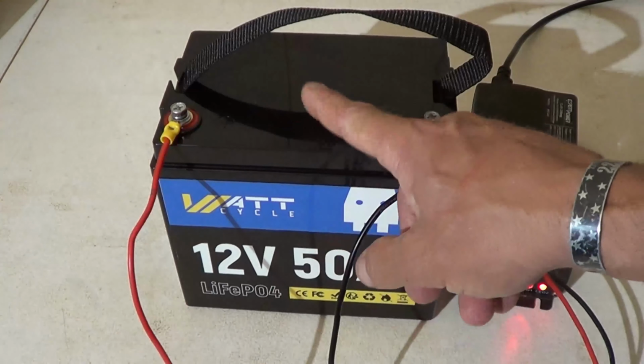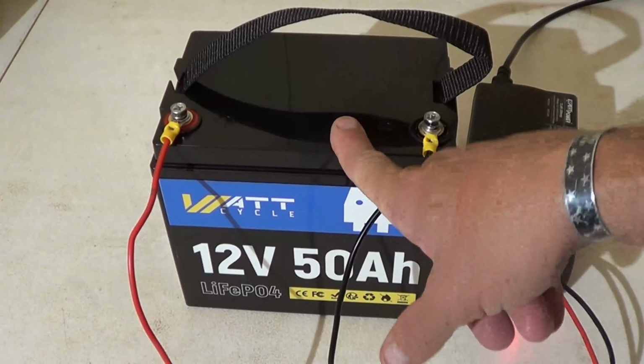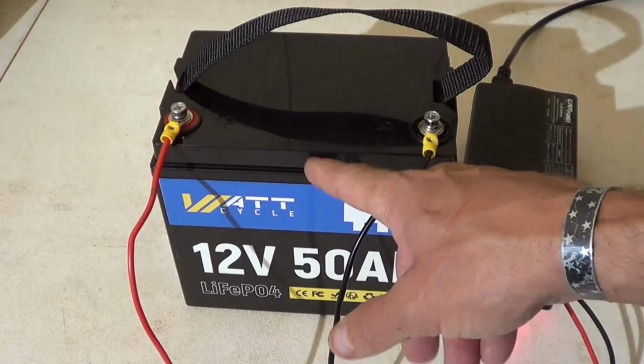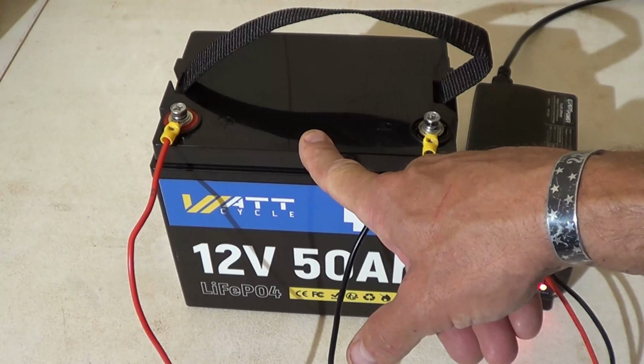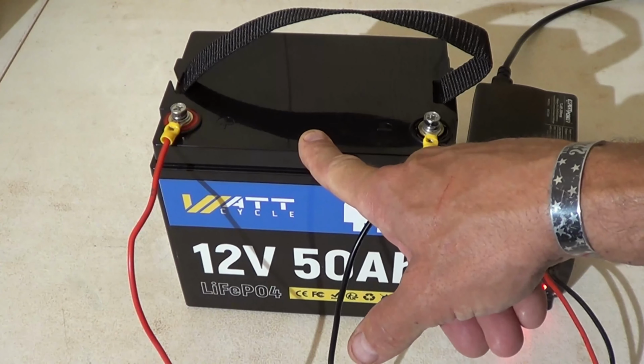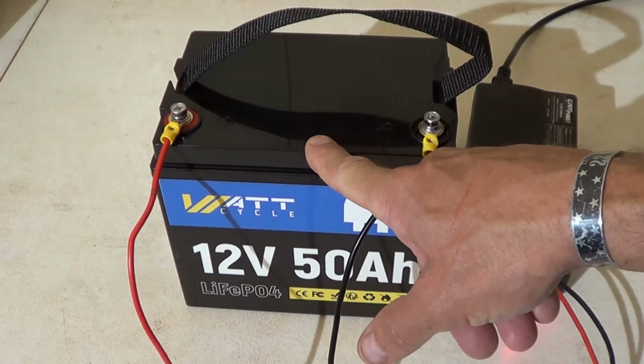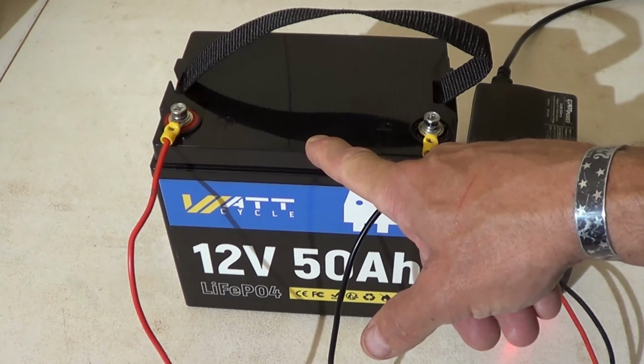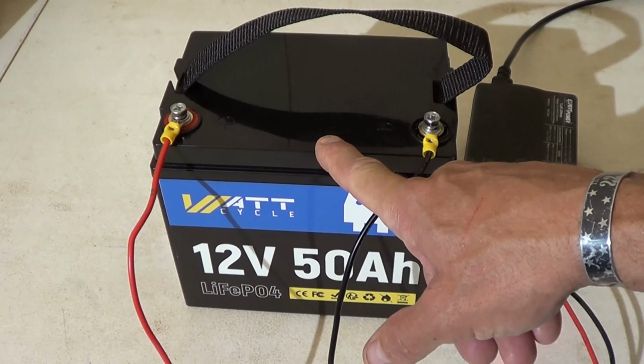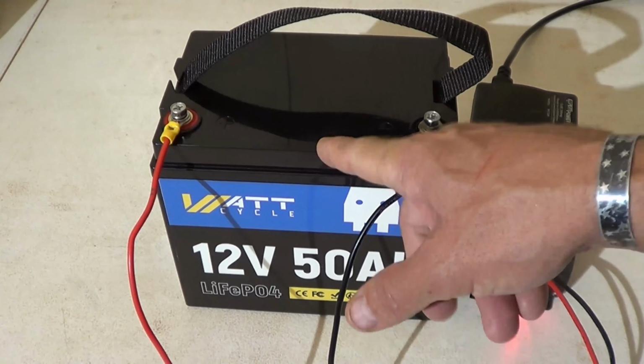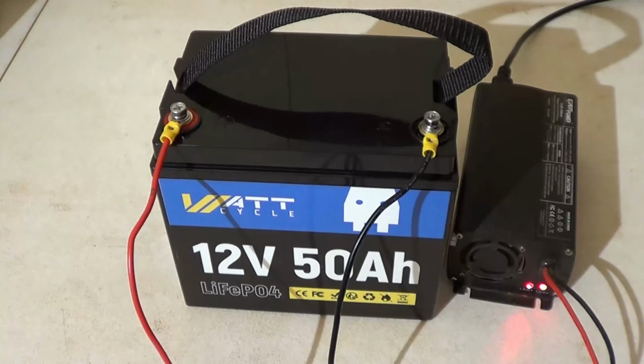Now, cell balancing is pretty important when you're going to do any of these batteries in configuration. Say you're going to put 4 in parallel or 4 in series, you want to make sure that you charge each one individually. A passive balancing process is activated by the BMS at the top of each charge cycle, when the battery voltage exceeds 14.1 volts. This ensures that all the cells remain in the same state of charge, which helps the battery pack performance.